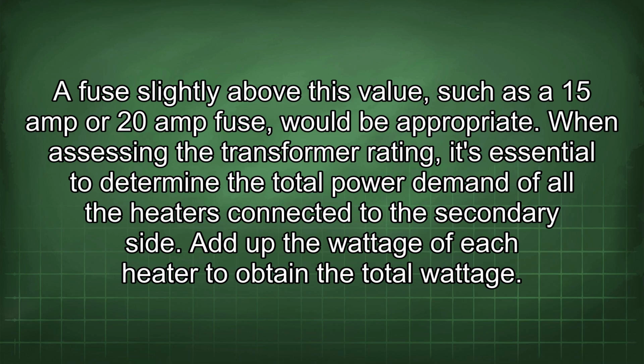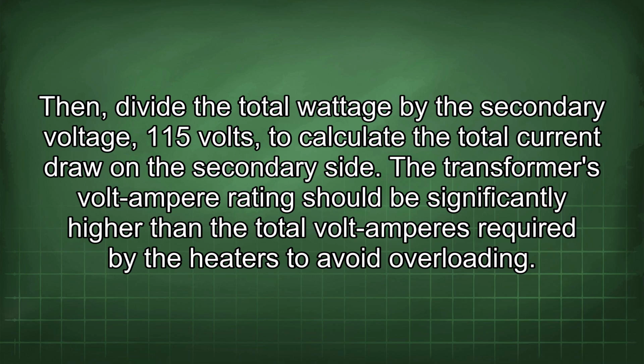When assessing the transformer rating, it's essential to determine the total power demand of all the heaters connected to the secondary side. Add up the wattage of each heater to obtain the total wattage. Then, divide the total wattage by the secondary voltage, 115 volts, to calculate the total current draw on the secondary side.